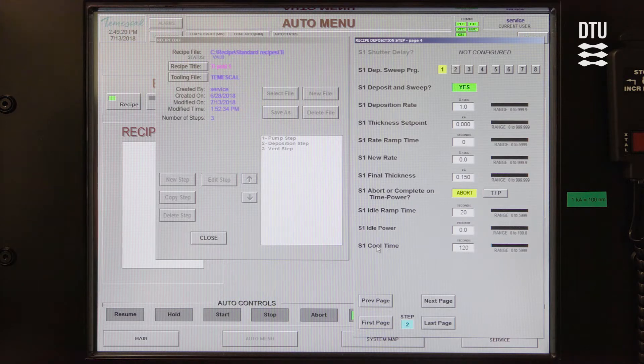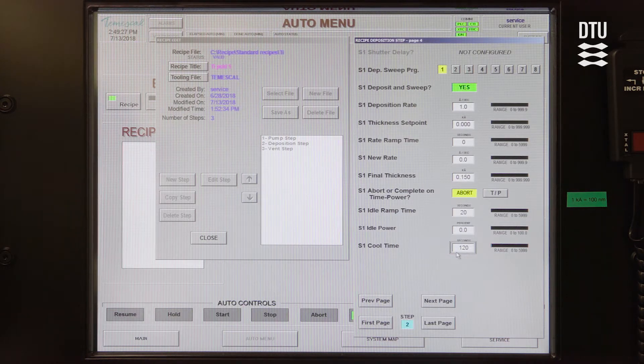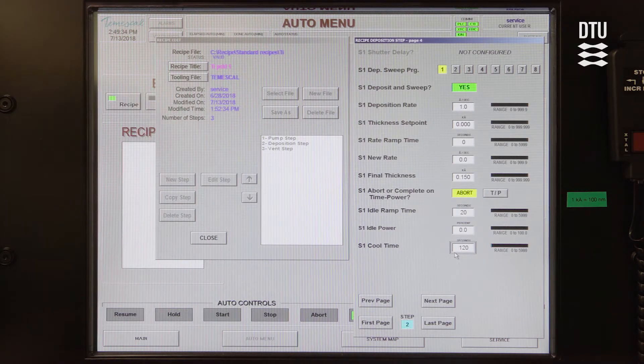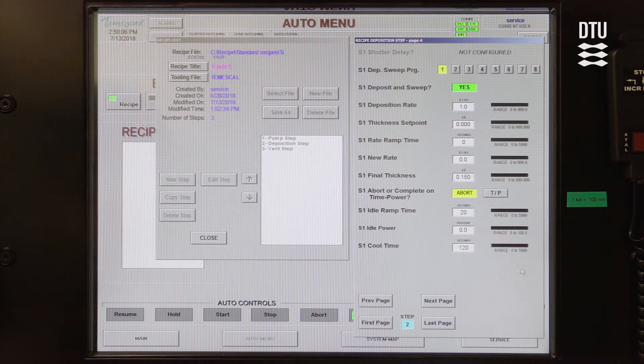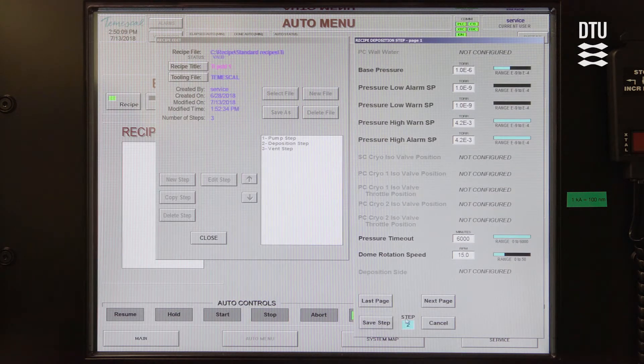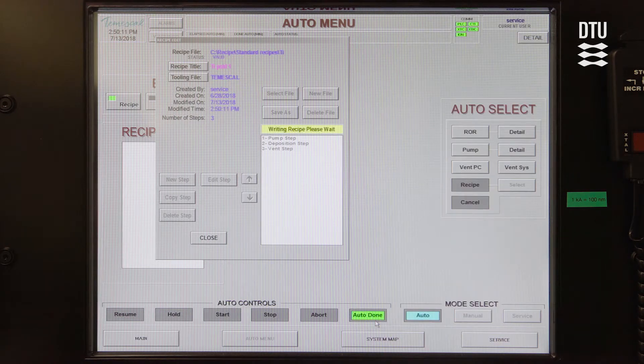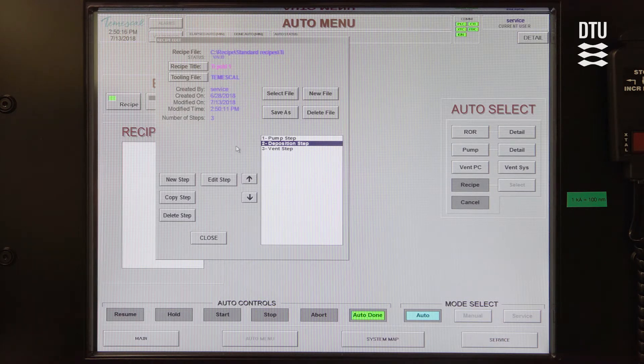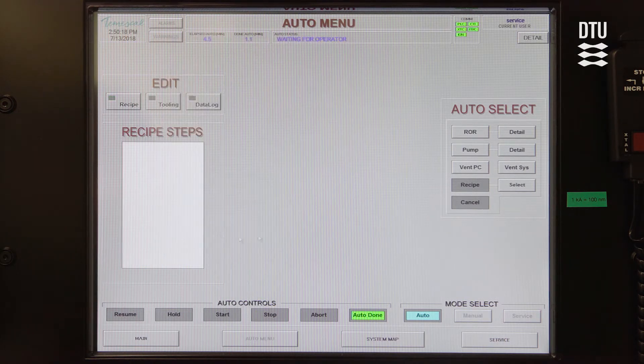The last thing you can change on this page is the cool time. Right now it's set to let the wafers cool off for two minutes before the end of the process, and at the end of the process the chamber is going to vent. Now you've made some changes and you need to save them — go to the first page and click Save Step. Your changes are now saved and you can close the recipe.